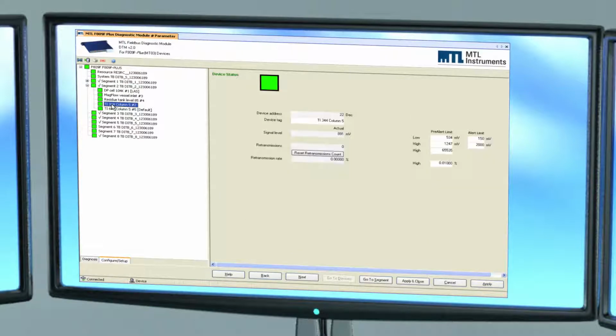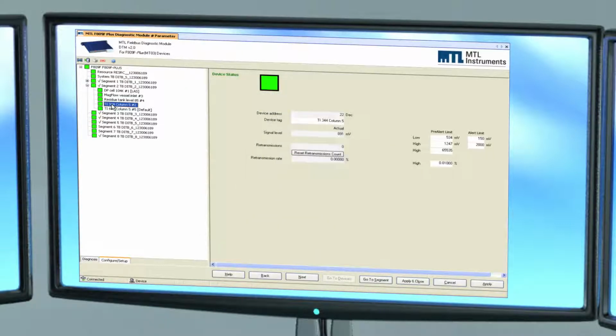Within a segment, individual device parameters can be inspected by clicking on their respective names within the tree view. Here, the signal level and address of the device with tag TI344 column 5 are displayed. This is a healthy device, as indicated again by the green NAMUR symbol. Note again that the pre-alert and alert limits for the signal level and retransmissions rate and count are displayed in the Configure/Setup tab view.